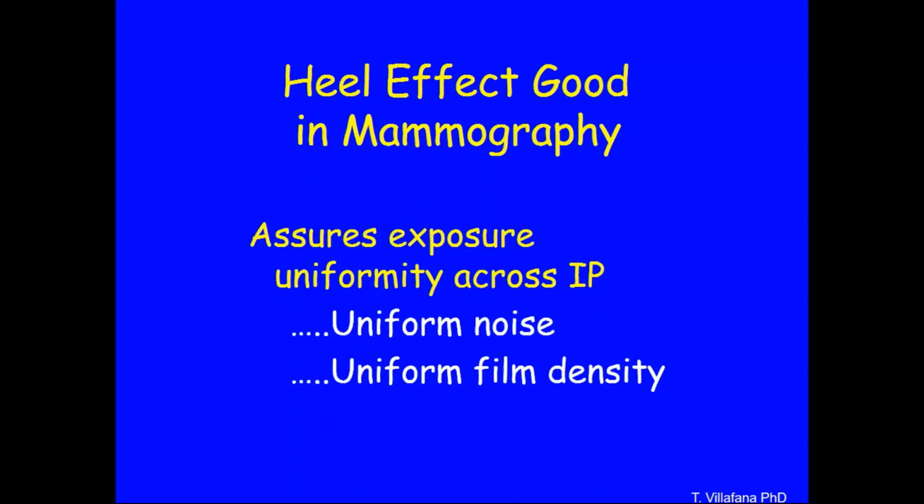If you had old-fashioned film mammography and a non-uniform beam, what do you actually see in the image? A non-uniform beam would mean that over at the anode side, where there's very little radiation, there's very little density. You can't see anything because the film density would be so low. Over on the right-hand side, where there's lots of radiation intensity, there you will see your image. One end of the image would be cut off, very low film density, very light, while the other would have its full film density.